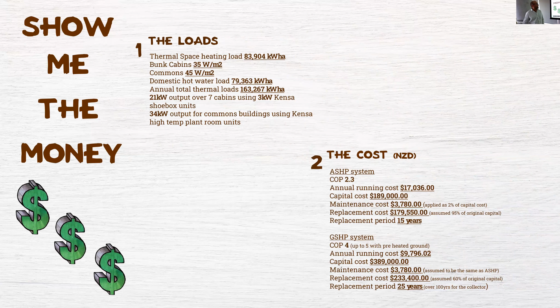So some numbers, it's always the dreadful bit. First of all, the loads. We've got a thermal space heating load of 83,904 kilowatt hours annually. That was over the cabins and the common building, so that was our total load. Again, with all of the work that was done to passive build the buildings, that was probably about a fifth of what it would have been on a normal project. So we've really managed to drop our loads before we even started. That was about 35 watts a square meter for the cabins, and the commons was 45 watts a square meter.